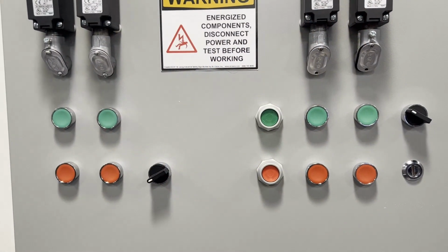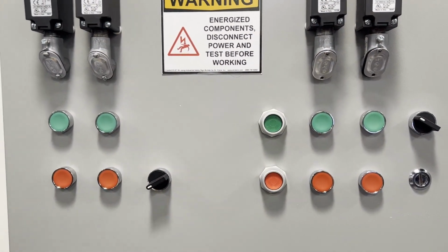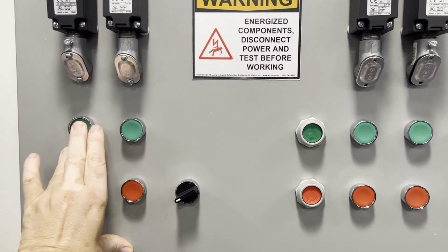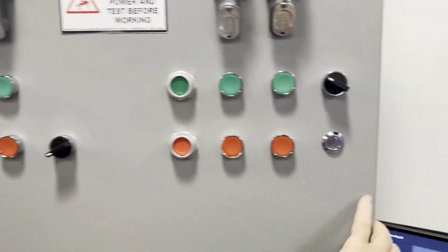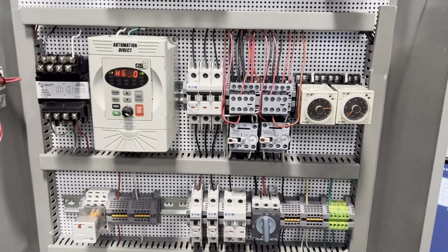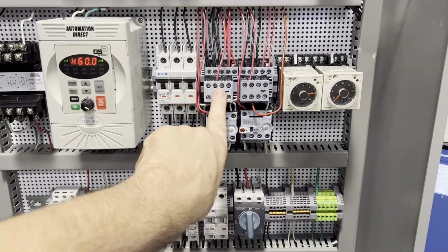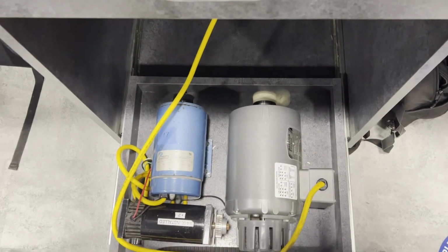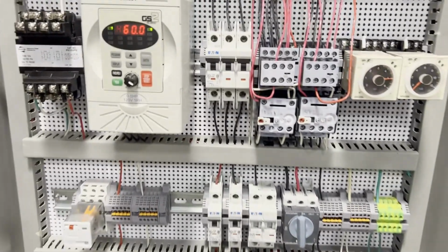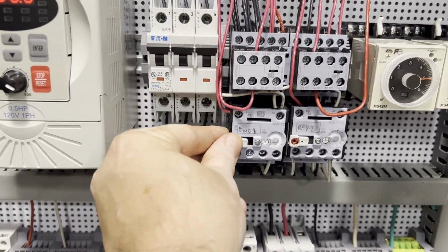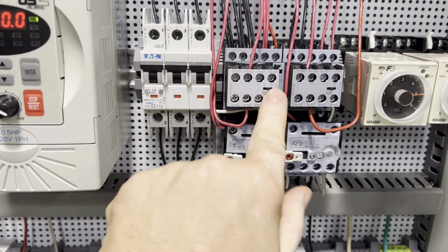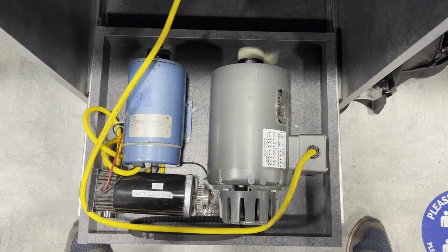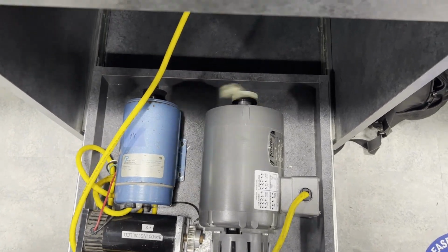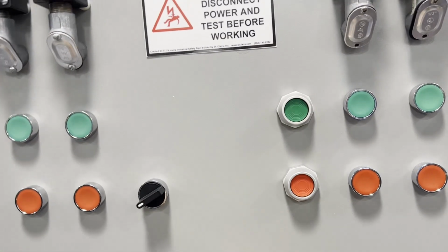Test number 3, forward overload. Start motor in the forward direction. Verify forward contactor closed. Motor rotating forward direction. And we push the forward overload. Observe the forward contactor open. And motor coasting down to stop forward direction. That concludes the forward overload test.